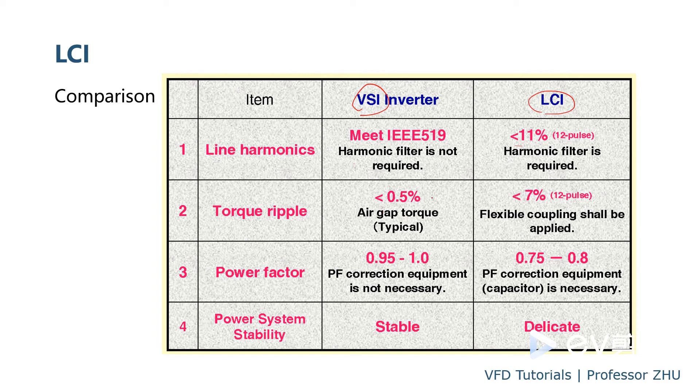In those areas, still use LCI in a lot of cases. Especially for the drive on the conditions that the drive will run for a long time, always running, people will prefer the VSI. Some comparison for the harmonic. VSI drive, the power factor is very good because they use a diode as a rectifier. Normally very low degree of lagging between the input current and the voltage.